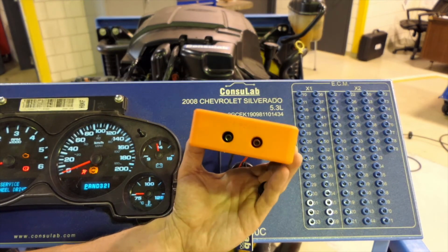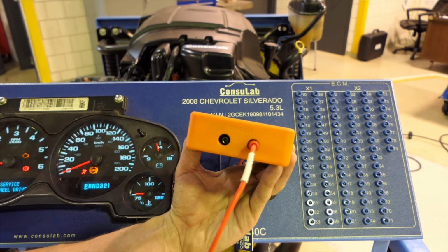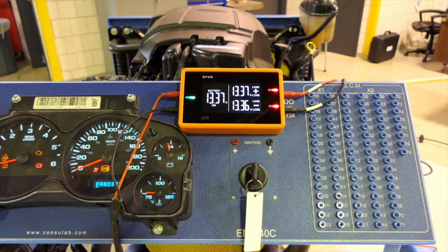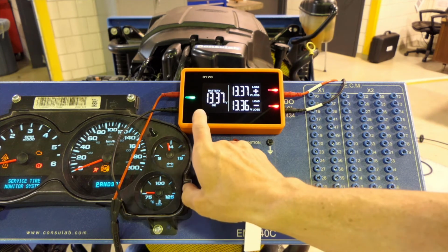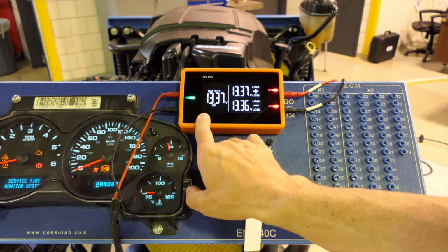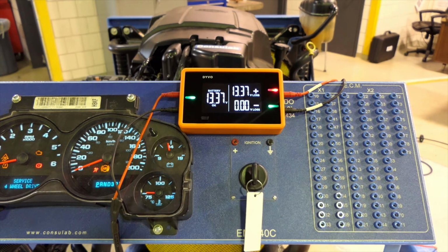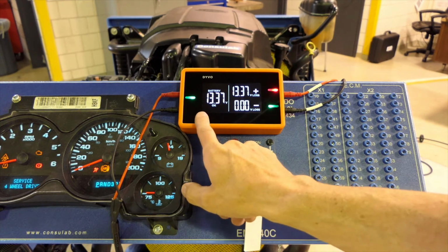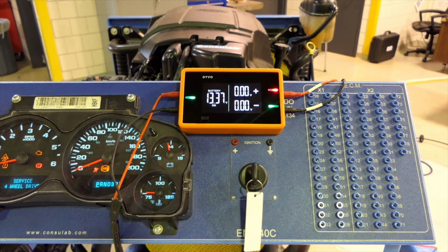On the right side it says circuit, and that's the side I'm going to connect my circuit test leads to. Because I'm testing a sensor, I'm going to take DYVO out of load mode by pushing the mode button down for 3 seconds until load disappears. Then I'm going to press the mode button one more time to cycle it to voltage available.